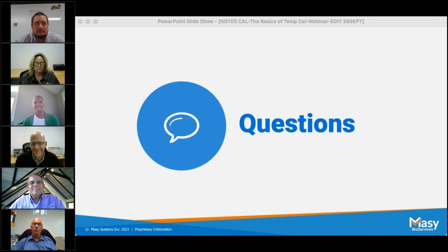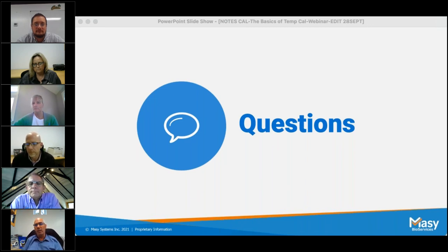Awesome, great answer. Okay, I have one last question and one last call for questions from the audience. If you have any other questions, send them in now. So for our last question, recommendations for avoiding past due calibration. Bob, can you give us an answer for this maybe? Yes, there are several ways to avoid past due calibrations. Have a database that will maintain your calibrations and your intervals and automatically give you reminders. Pay attention to the calibration labels that are on the devices, which will also give you a visual reminder, or you can hire a company like Masy who will send out periodic reminders.